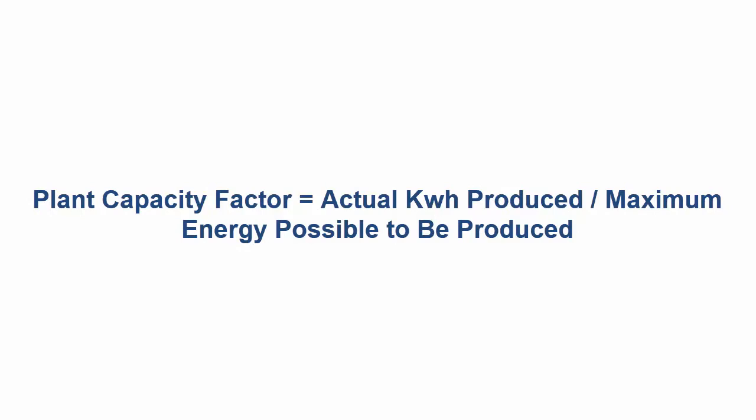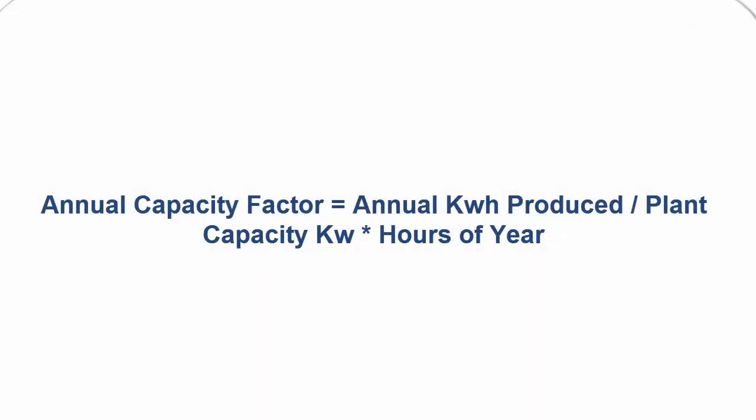The plant capacity factor is the ratio of actual kilowatt-hours produced to the maximum possible kilowatt-hours if the plant operated at full capacity. This is similar to the utility factor but expressed in kilowatt-hours, indicating how much energy was produced versus the maximum possible if all generators ran at full capacity. If this is calculated over one year, it is termed the annual capacity factor — the annual kilowatt-hours produced divided by the maximum plant capacity per year.